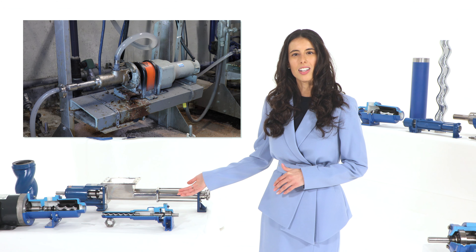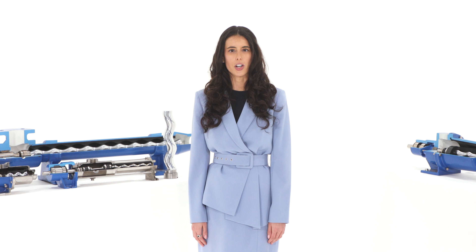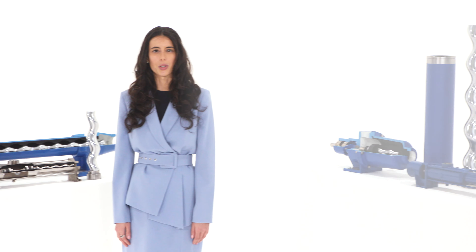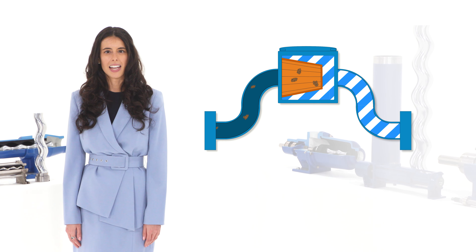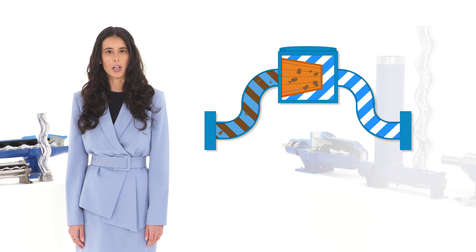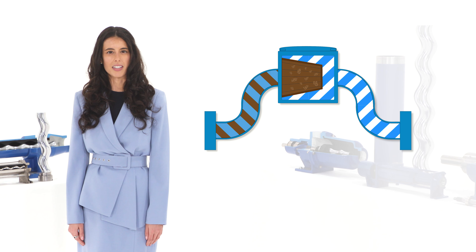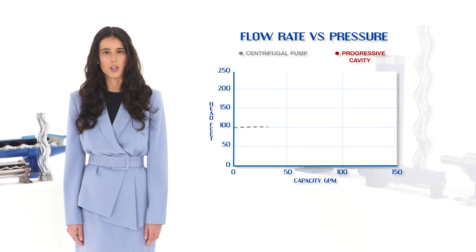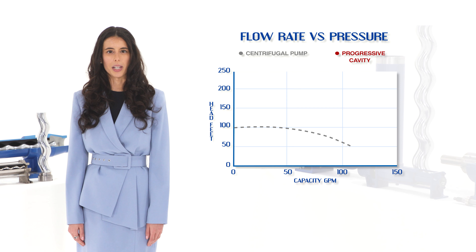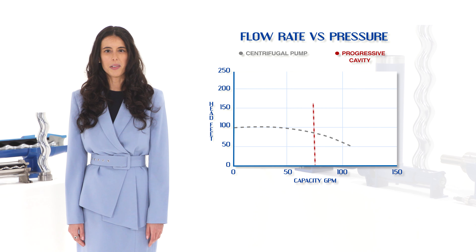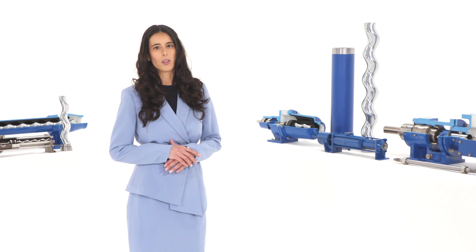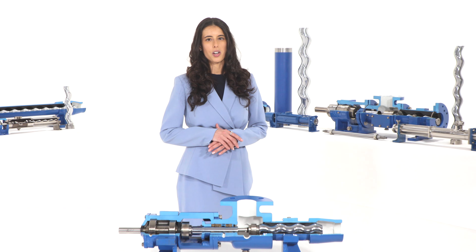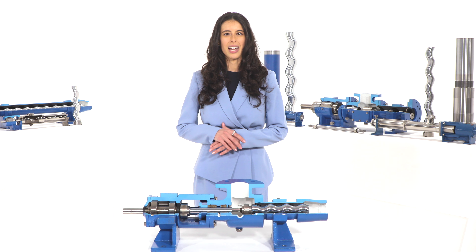Constant flow with varying discharge pressures. Progressive cavity pumps are also ideal for pumping applications where the discharge pressures vary, such as pumping into a filter to remove solids from a liquid. As the filter loads, the discharge pressures the pump must work against increases. Other types of pumps have an inherent difficulty pumping against varying discharge pressures, and some will even stop working. But not the progressive cavity pump! A PC pump will have the same flow regardless of varying discharge pressures and will continue to pump as long as required.